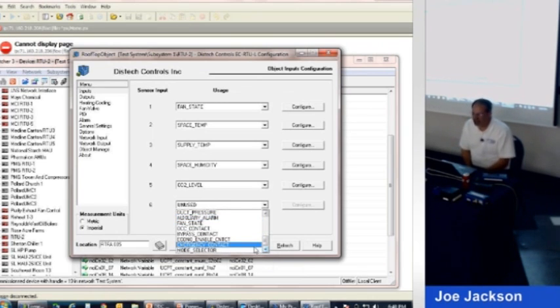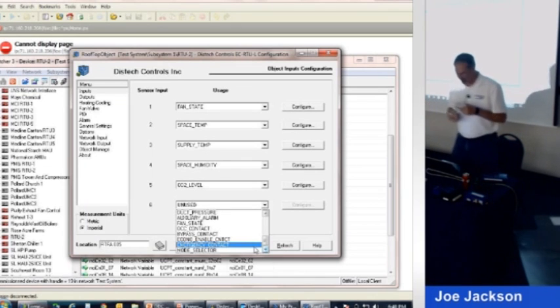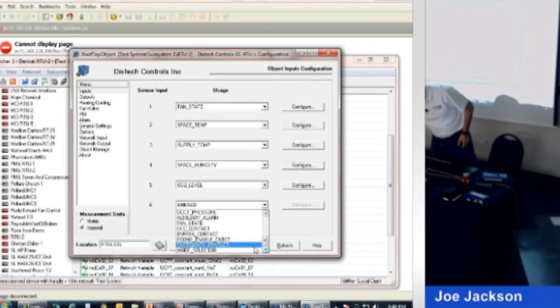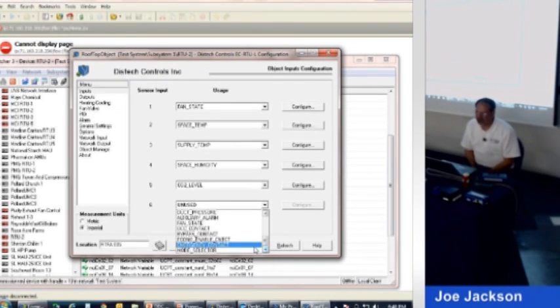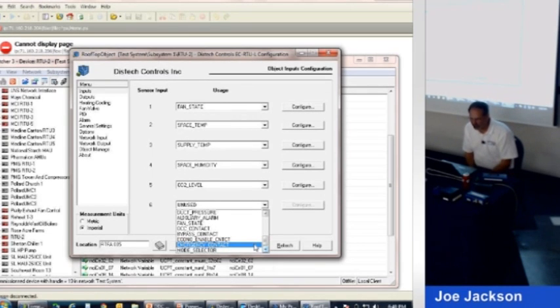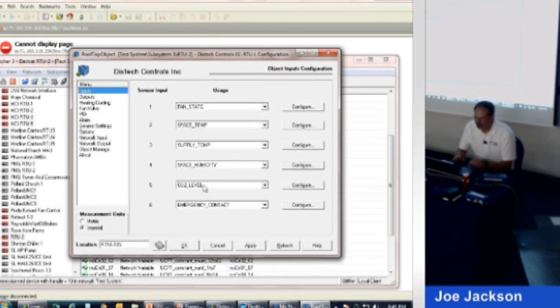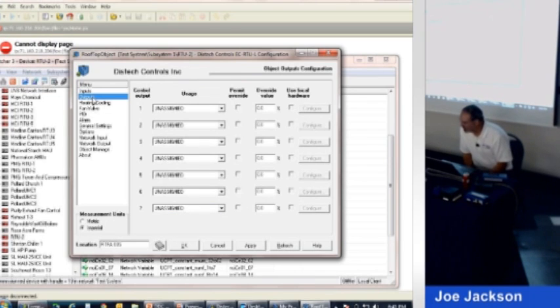Emergency contact, that just shuts the rooftop down. Maybe it could be a freeze stat, it could be a smoke detector, whatever it is. If this contact goes open, it shuts the rooftop down. Most likely on a standard rooftop, it would be a smoke detector. And you could wire the smoke detector directly to the unit, and probably the right thing to do is run it through a relay and wire it directly to the unit, plus bring it up into the controller so that from down at the main computer you can see if the smoke detector is in alarm or not. So we'll add that guy there. So there's all the inputs we decided to put on our controller. And along with inputs, every rooftop unit's got to have some outputs. So what are the things that a rooftop has to turn on?